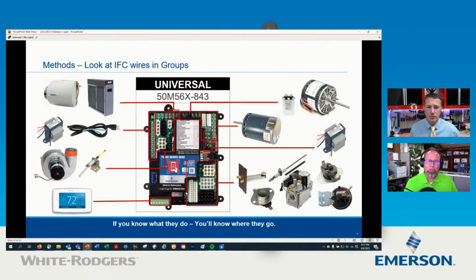And I say groups because a lot of times what you want to do is, I got the old board here. I'm pulling one wire off and I'm putting it over here. And we do that because we don't really know what's at the other end of that wire. But if we know these are all blower wires, let's pull these blower wires off and set them aside as a group. Yeah, exactly. We know that this is the igniter and the inducer wires. Let's set them over here together. This is the Molex plug or the inline plug. Let's pull this down here by itself.